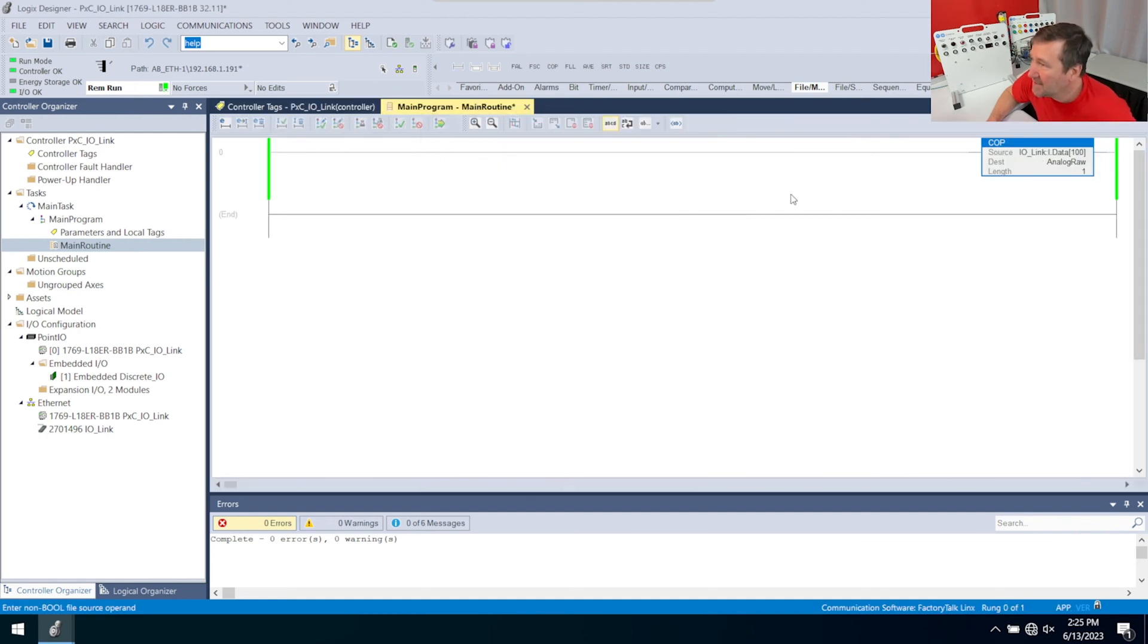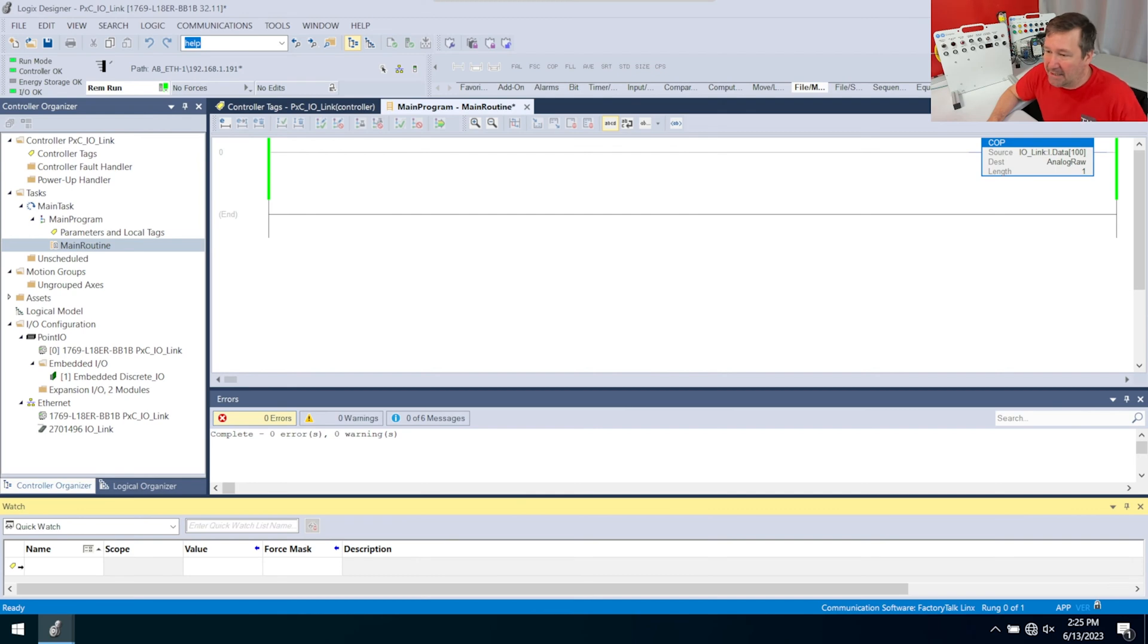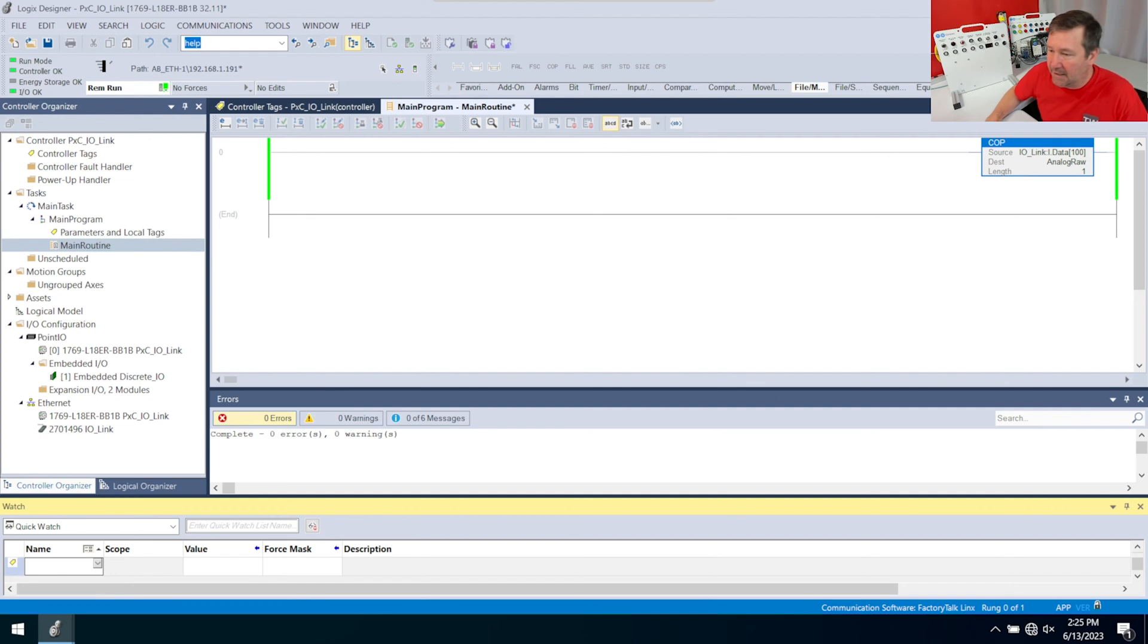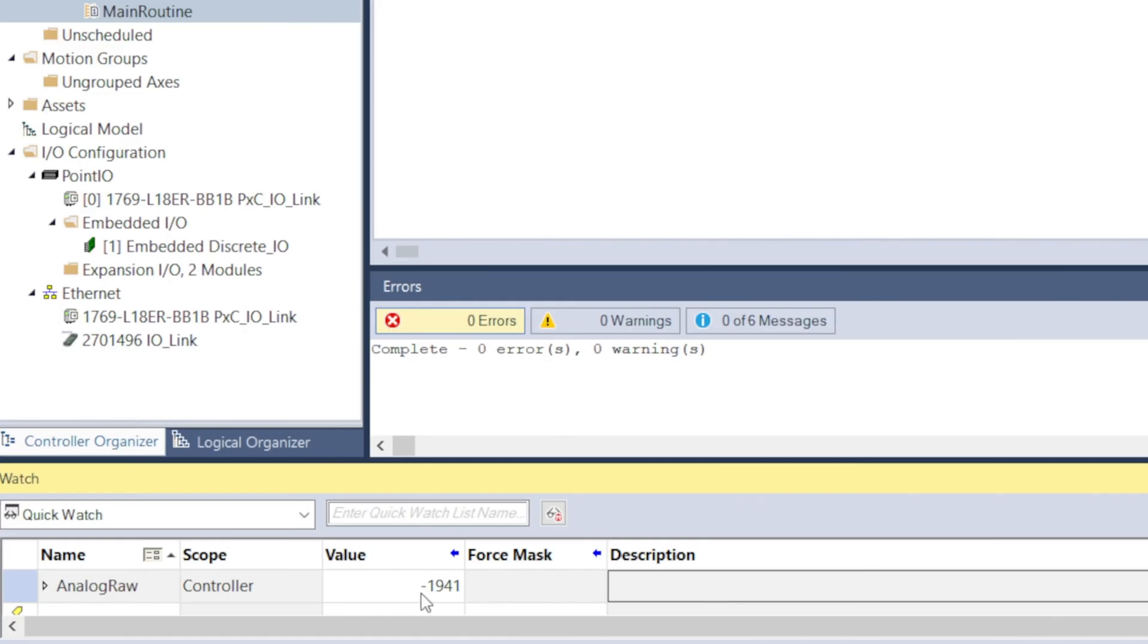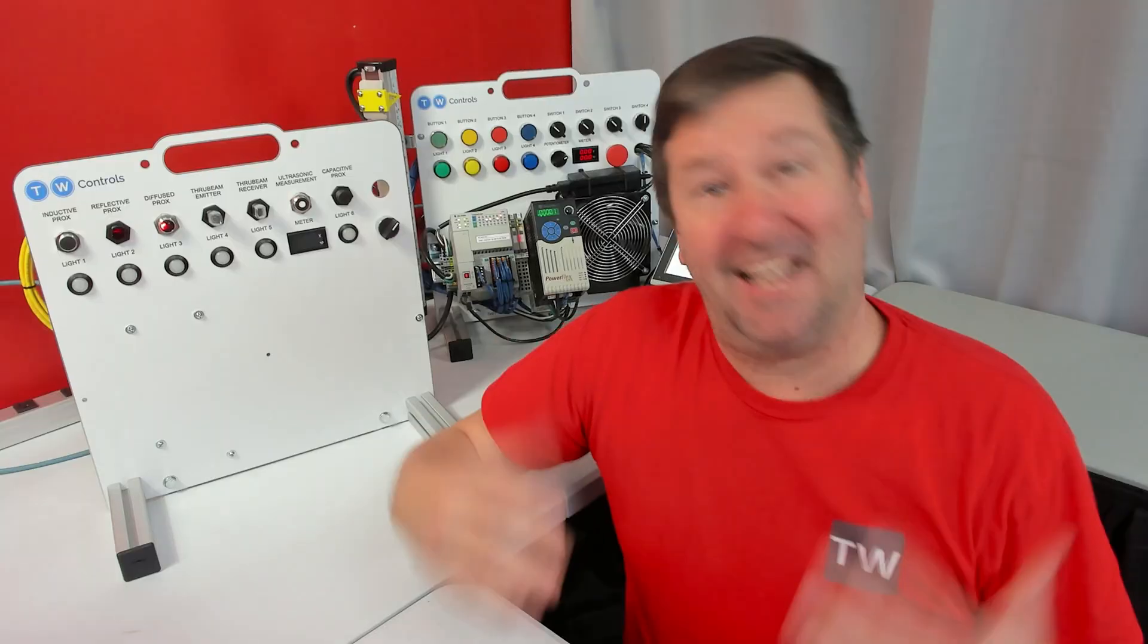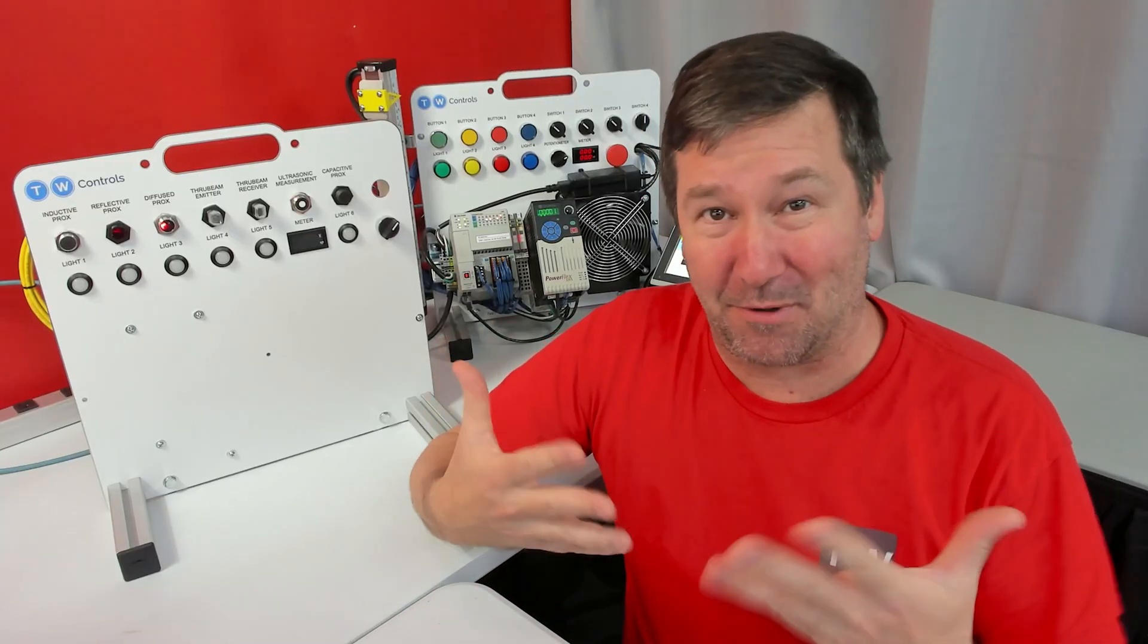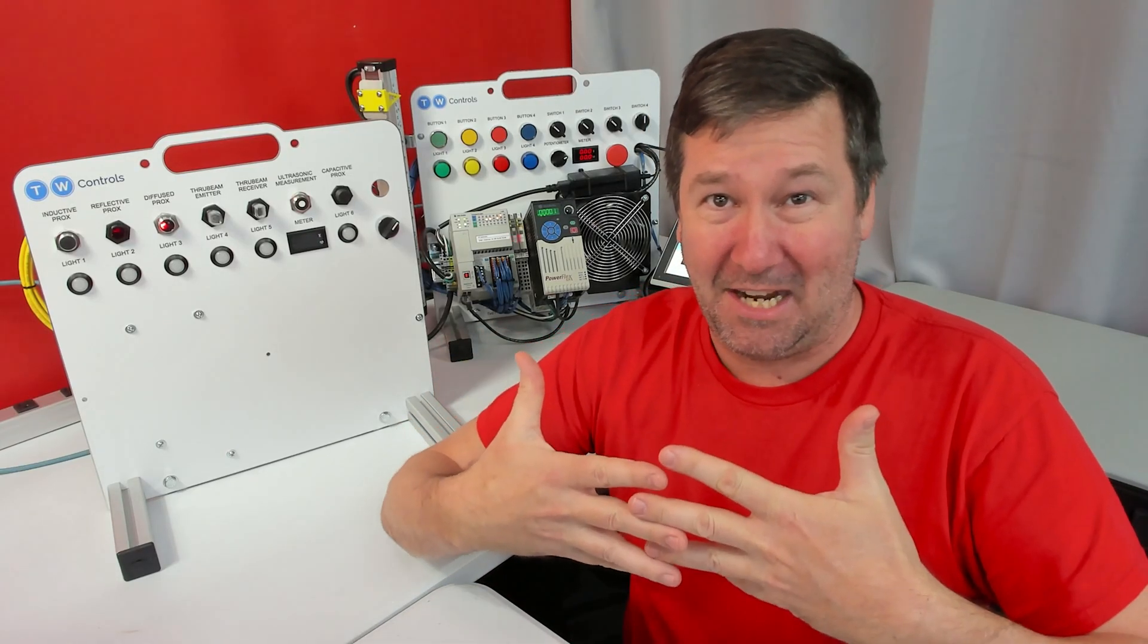So we can see this value while we're doing this work, let's go to view and watch. Down here at the bottom, I'm going to put AnalogRaw in. That's going to give us the value of that. Notice while we're sitting here, it's bouncing between a negative 1,900 and a negative 3,900. That's the first indication that we do not have the bits in the right order. A lot of times, this just takes a little guesswork to figure out how to line these up.